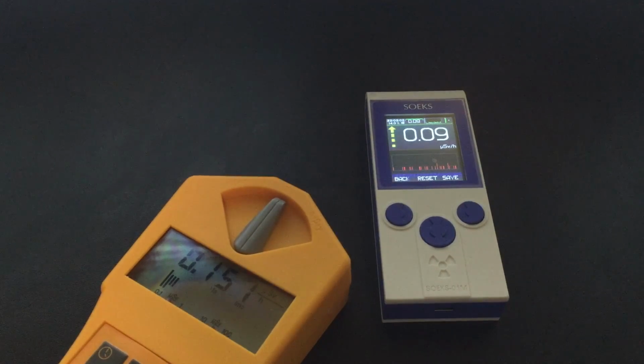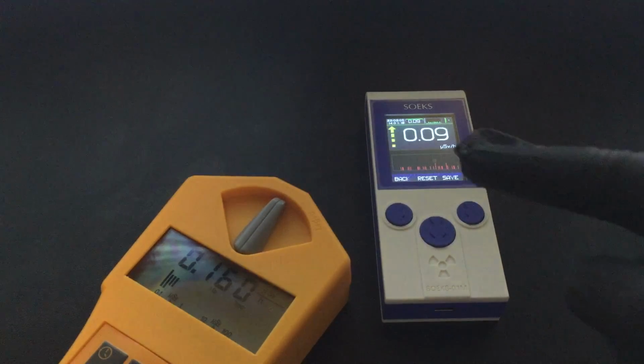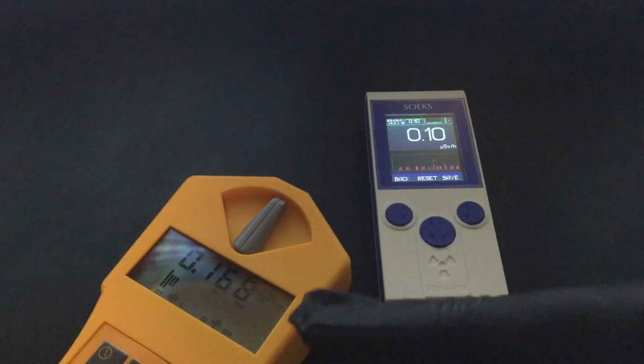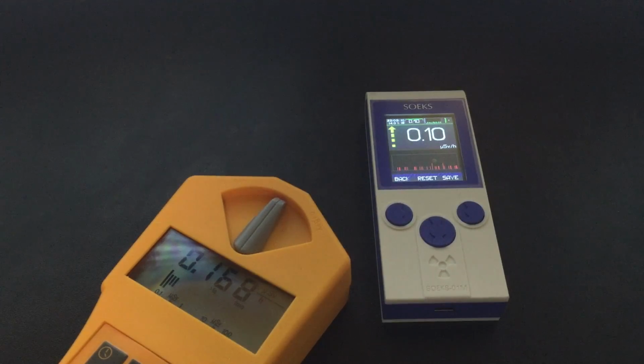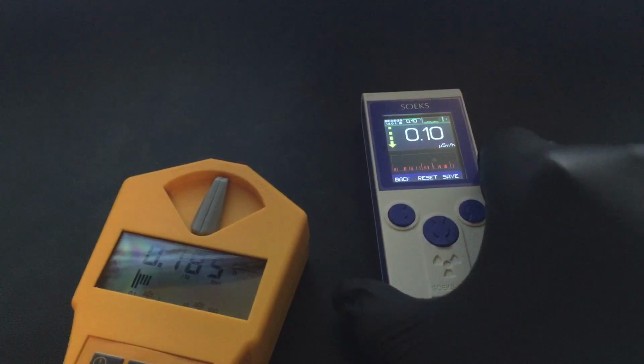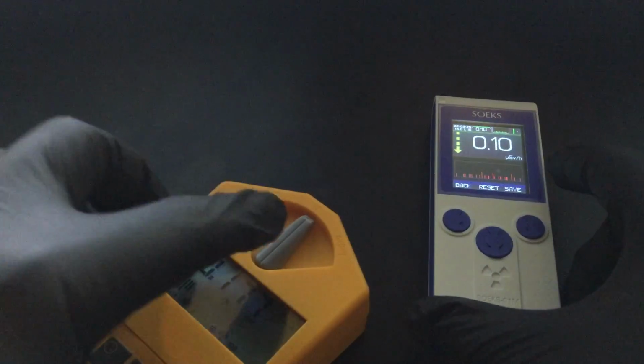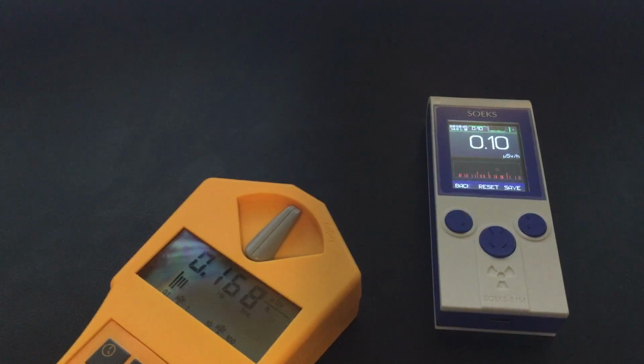Now, in this video, you can see I have this in millisieverts, and this is also in millisieverts. If you know before, I said don't have your meter in millisieverts unless you know what you're measuring. Well, this time I know what I'm measuring. Since both of these meters are calibrated for cesium-137, I am going to expose both of them to 10 microcuries of cesium-137, which you can see here. The tube is on the left, and the other tube is in the center here, so I'm going to drop it right here and we'll see what they do.